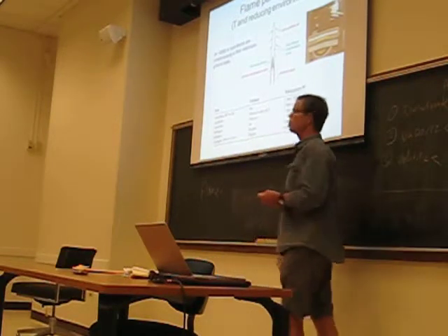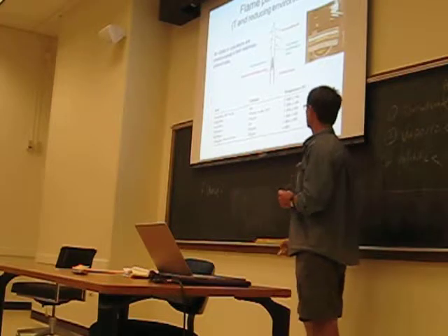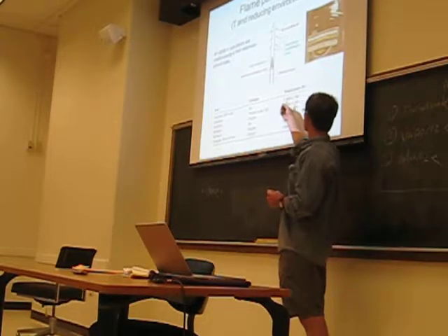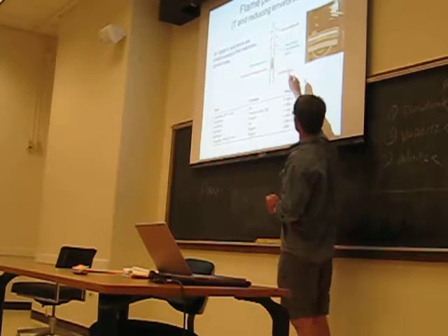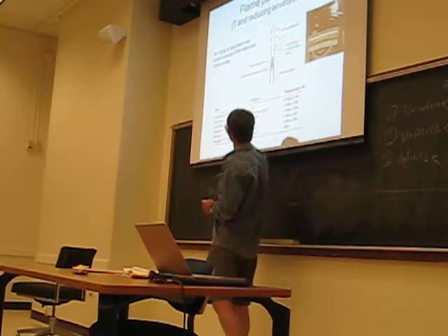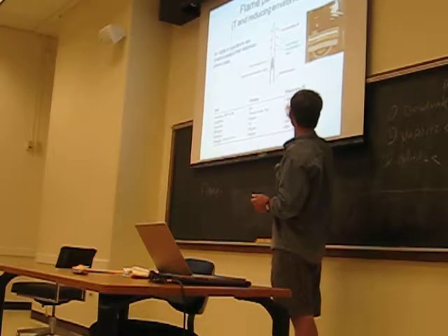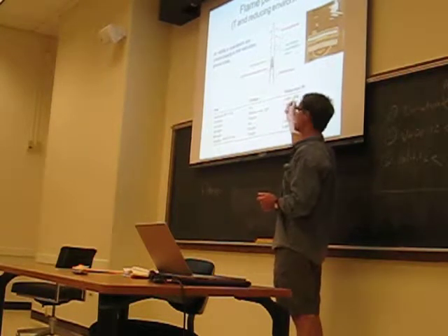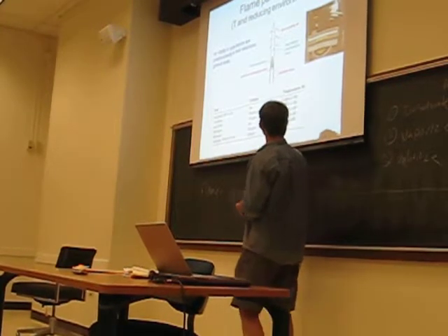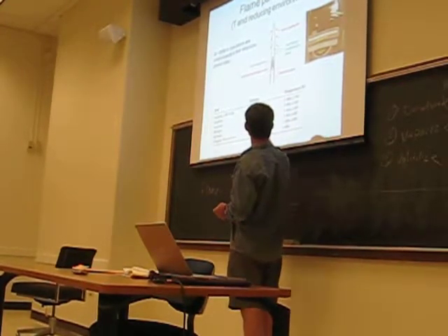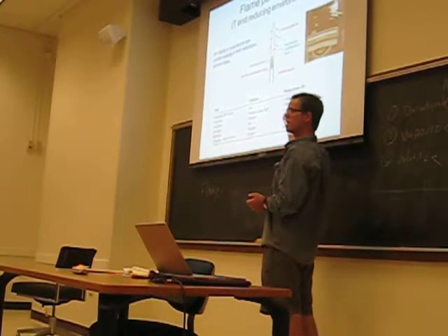Right? And depending on what the gas, oxidant and fuel mixture is, that determines to a great extent what the temperature of the flame is, and that temperature varies depending on the combustion zone. So if you're using acetylene and air, the temperature is about 2,400 to 2,700 degrees Kelvin. So it's pretty hot. If you need an even hotter flame, you might use acetylene and nitrous oxide, and it bumps the temperature up by 300 or 400 or 500 degrees K.